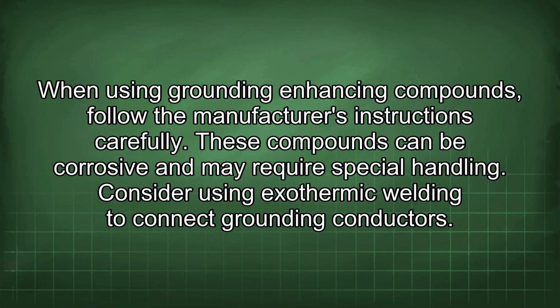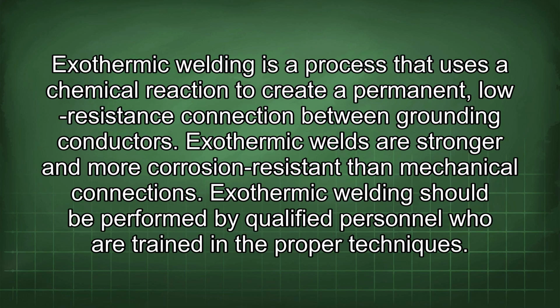Consider using exothermic welding to connect grounding conductors. Exothermic welding is a process that uses a chemical reaction to create a permanent, low-resistance connection between grounding conductors. Exothermic welds are stronger and more corrosion-resistant than mechanical connections. Exothermic welding should be performed by qualified personnel who are trained in the proper techniques.